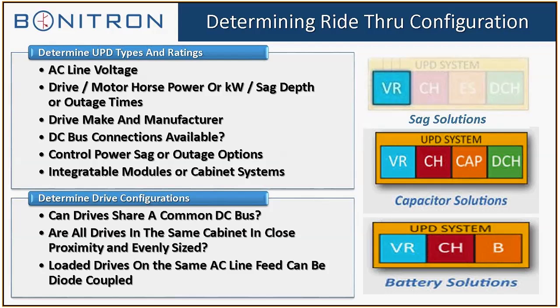Also, we can back up control power, but in a lot of cases the customer's already thought of that, and they'll usually use a small UPS or sag corrector on the AC line. It's usually single phase 120.